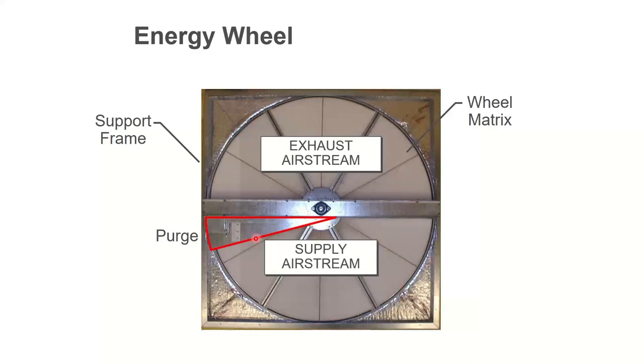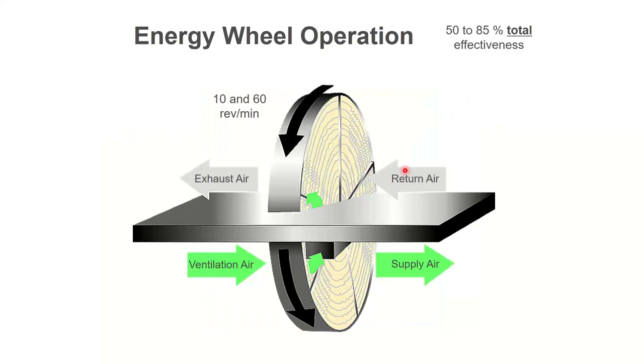So in this example, maybe the bottom gets warmed up and it rotates to the top where it releases its heat, turns back around, gets warmed up, rotates to the top, releases its heat. So those guys are spinning. There's one extra thing involved here. It's got a small motor on there, typically like an eighth horsepower or even smaller sometimes. It doesn't have to do a lot of work. It's just turning this wheel at fairly low revolutions.